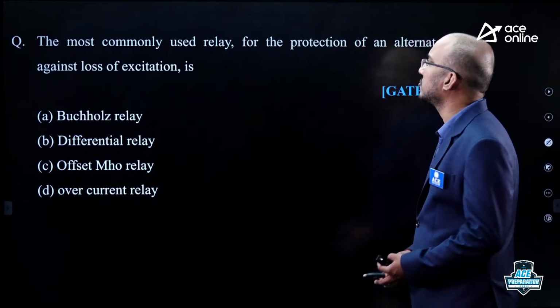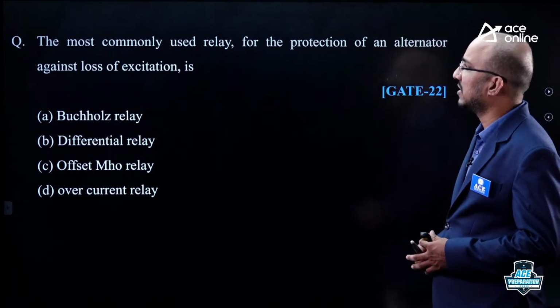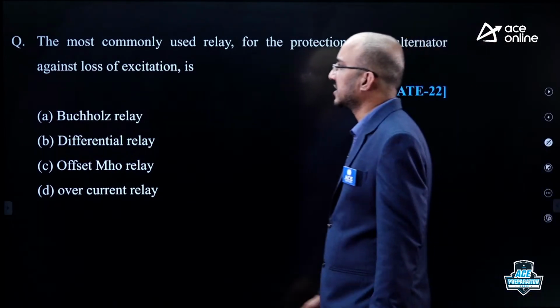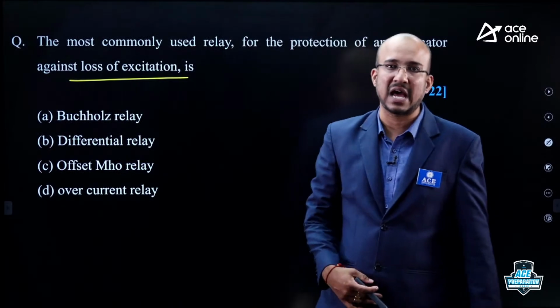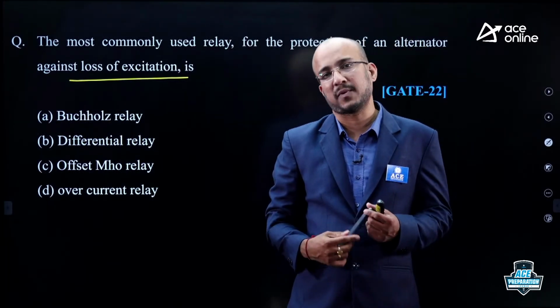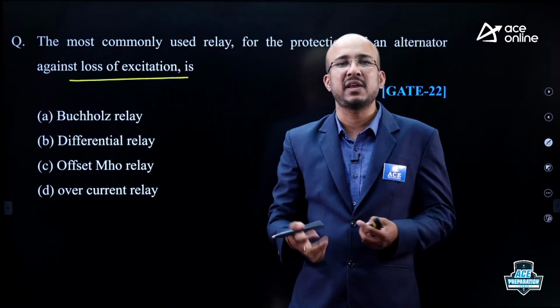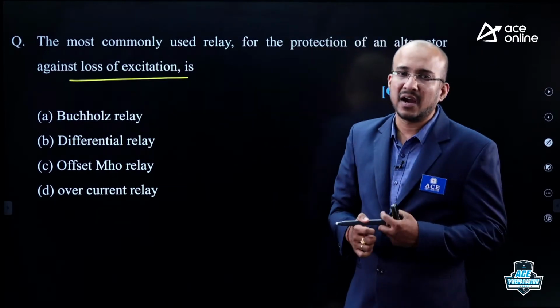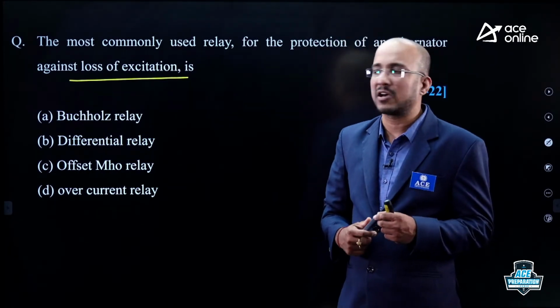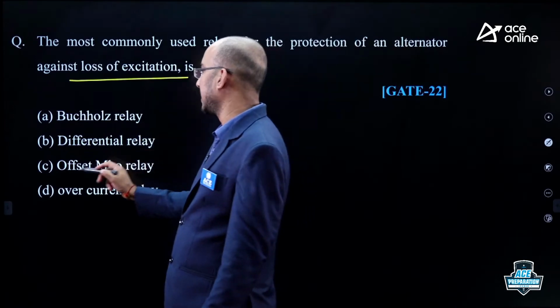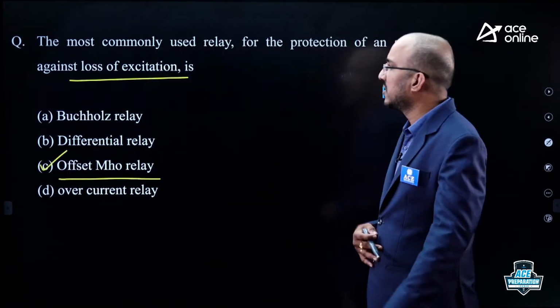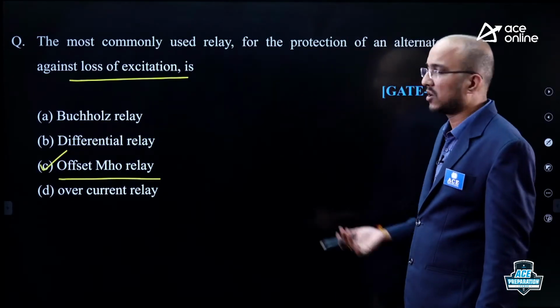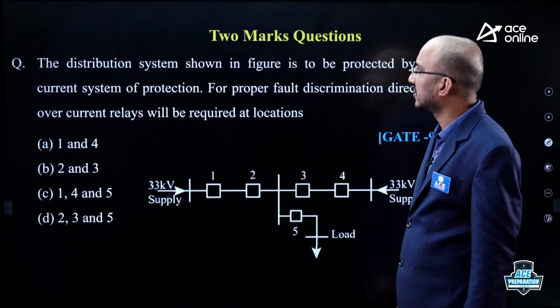The most commonly used relay for protection of alternator against loss of excitation. So, he is saying loss of excitation. When the excitation is lost and mechanical input is present, then the machine behaves as an induction generator. How do you protect the alternator from loss of excitation? We will be using an offset Mho relay. Offset Mho relay is used for protection of alternator against loss of excitation.